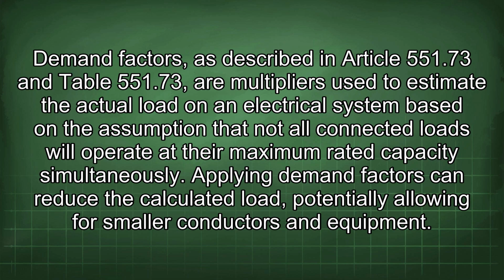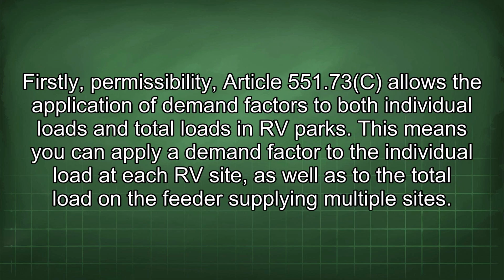Applying demand factors can reduce the calculated load, potentially allowing for smaller conductors and equipment. Firstly, permissibility. Article 551.73(C) allows the application of demand factors to both individual loads and total loads in RV parks. This means you can apply a demand factor to the individual load at each RV site, as well as to the total load on a feeder supplying multiple sites.